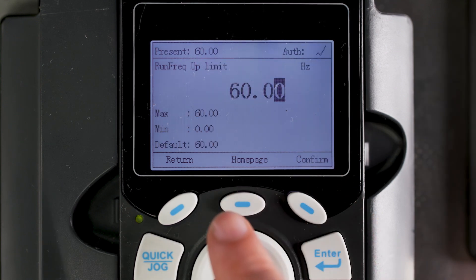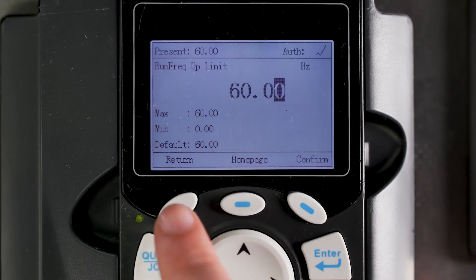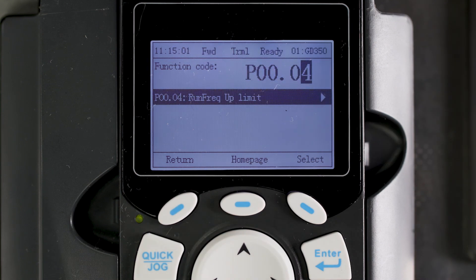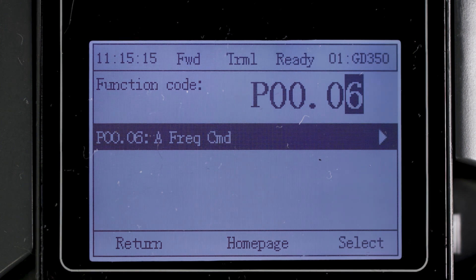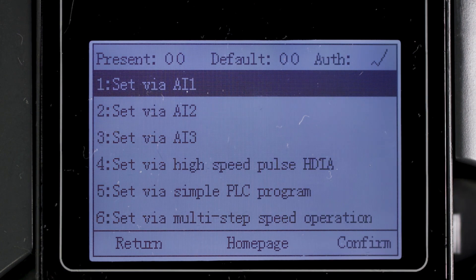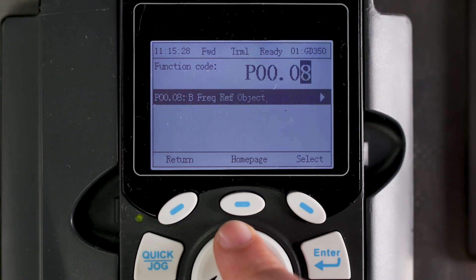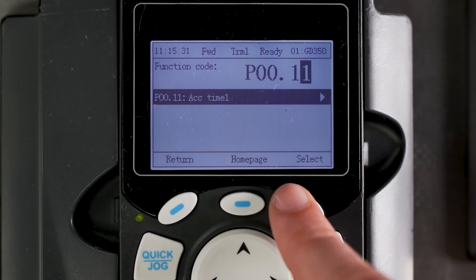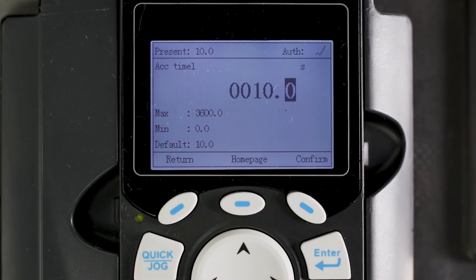If you are planning on running on a single set speed, the drive will ramp up to the maximum output frequency by default. .05 is used to adjust the maximum speed of the drive. .06 and .07 are used to adjust the drive's output frequency. If you have an analog input for speed control, then you can select value 1 on this parameter. .11 will change the acceleration time and .12 will change the deceleration time, both in seconds.